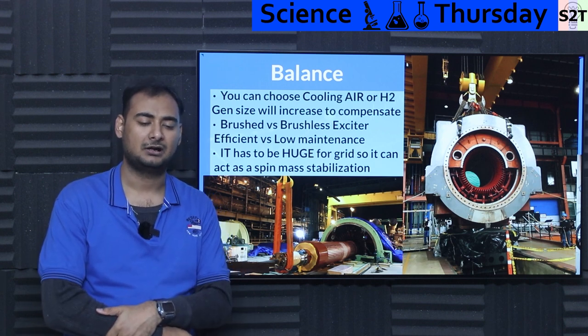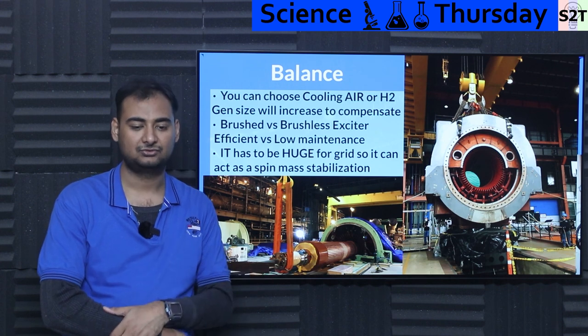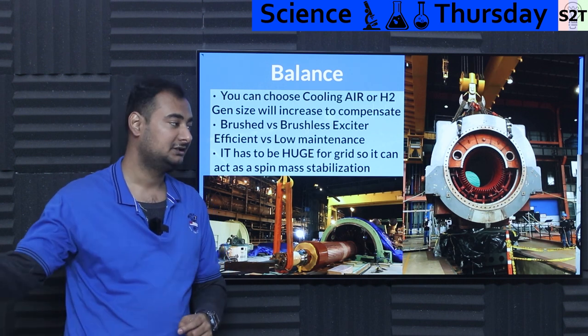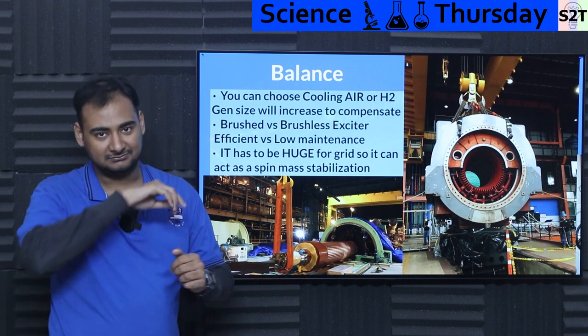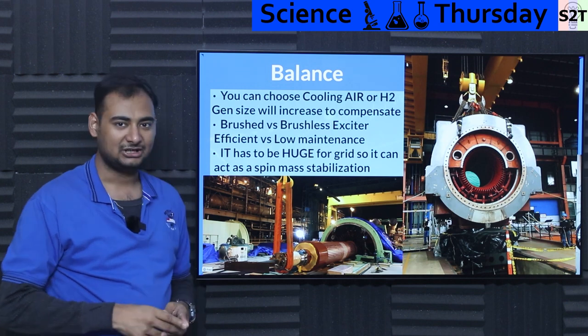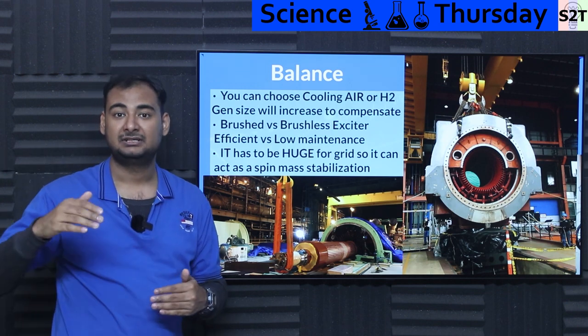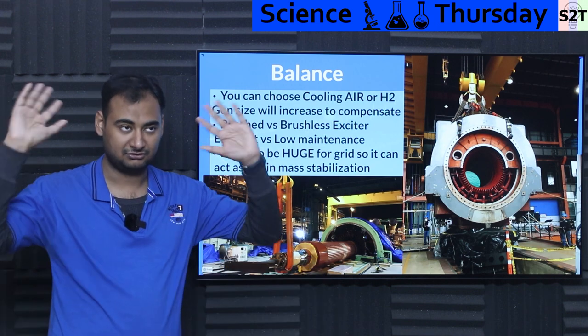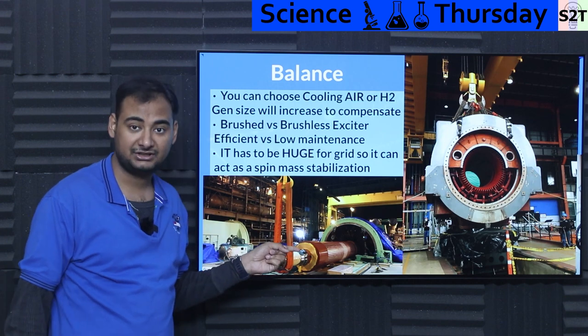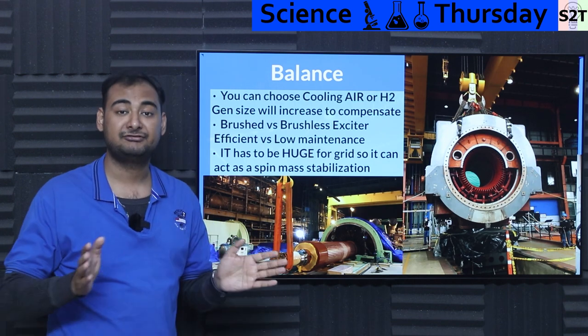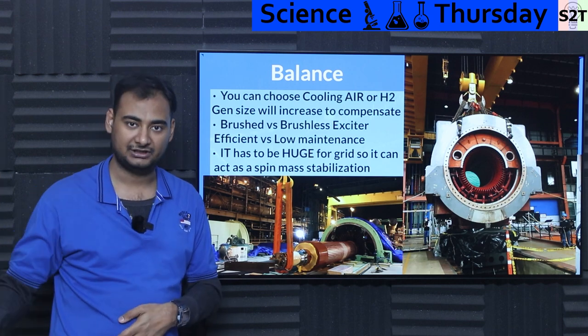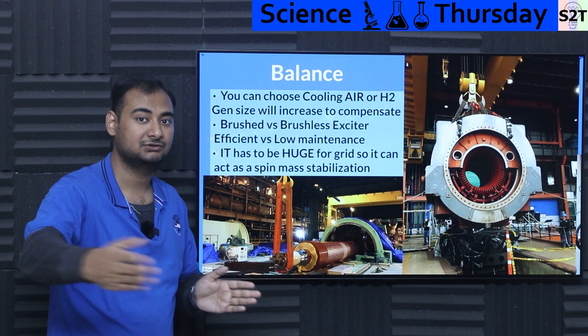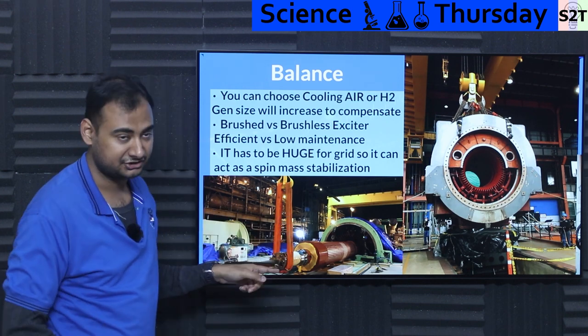The same works in reverse: if a cricket stadium suddenly shuts off all its lights, the RPM starts to rise, but inertia slows that change enough for the computer to detect it and reduce steam input. This isn't happening at just one generator — everything connected through the grid is coupling with this sort of inertia. That's why we have a stable grid. You do not want tiny generators; you want big, heavy generators — as big as you can transport.